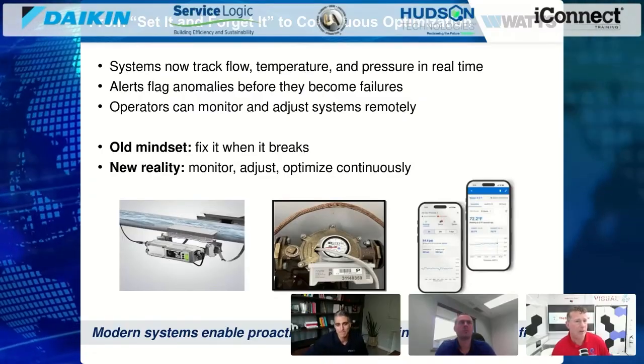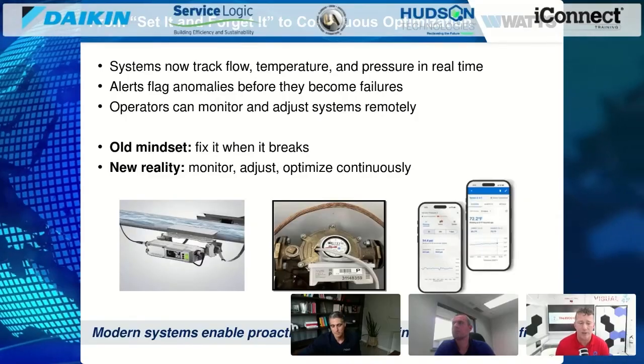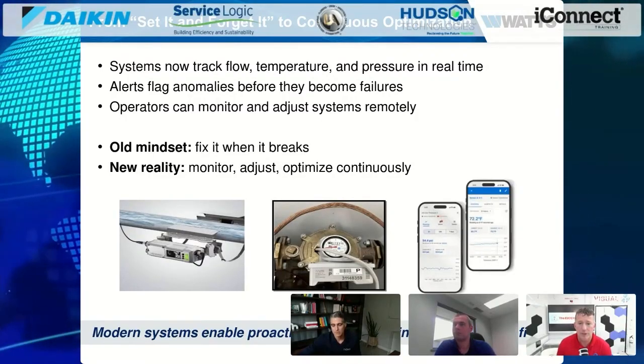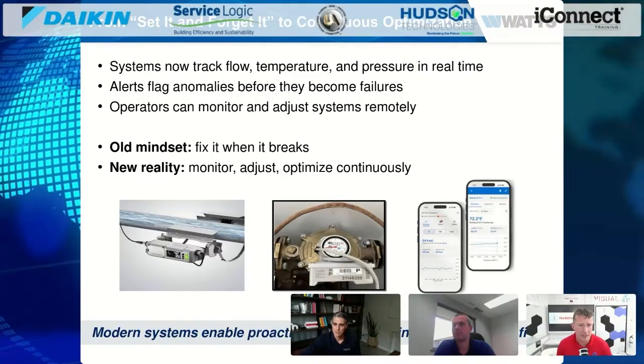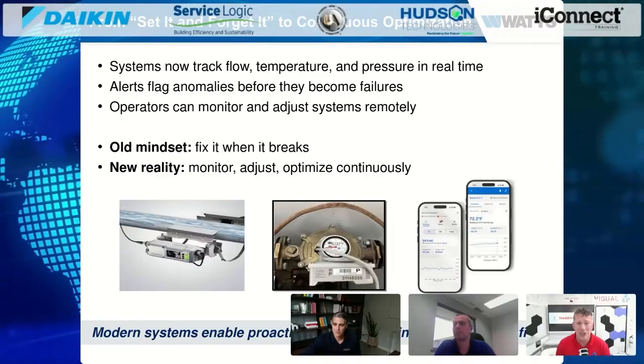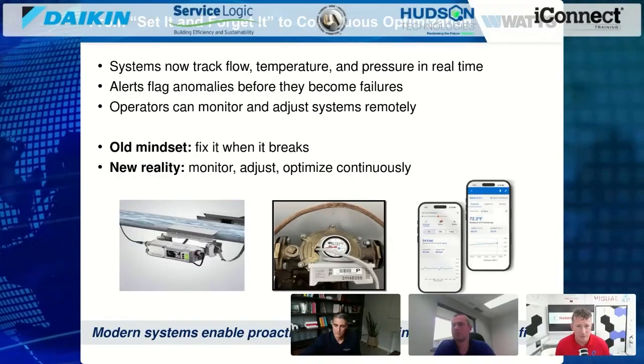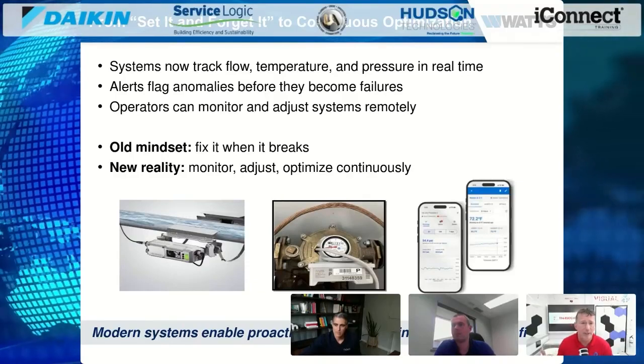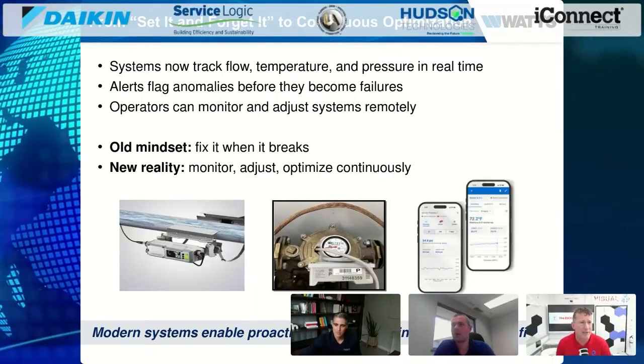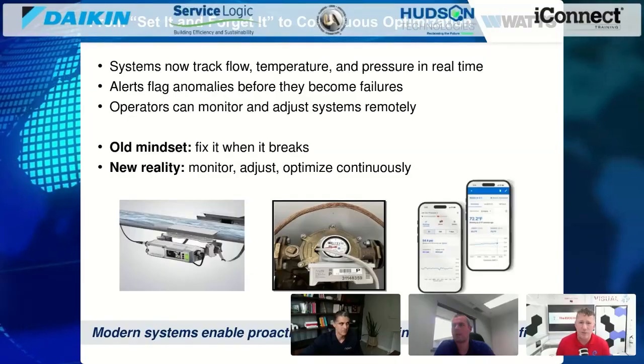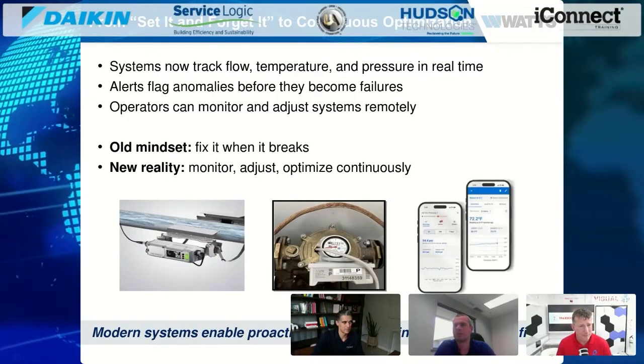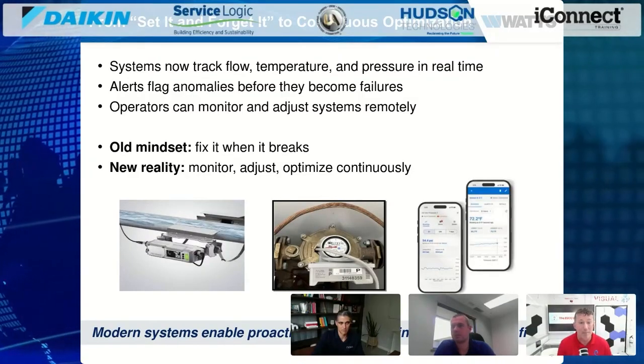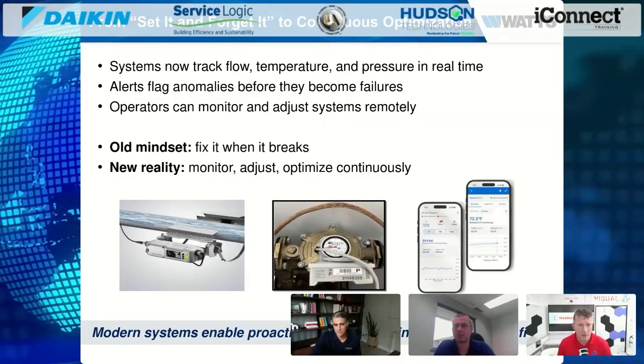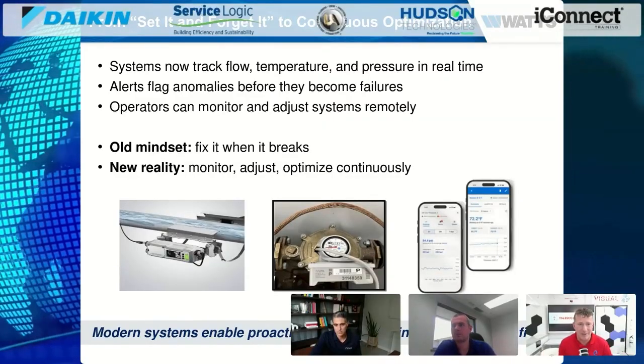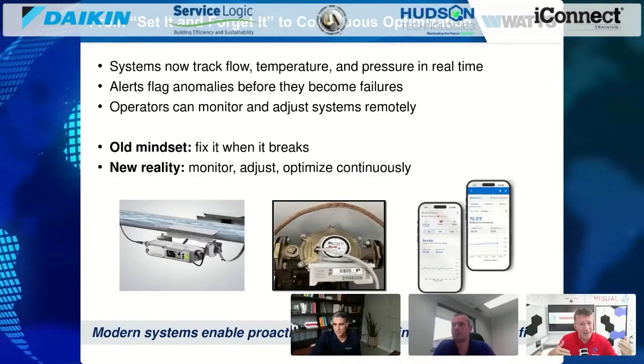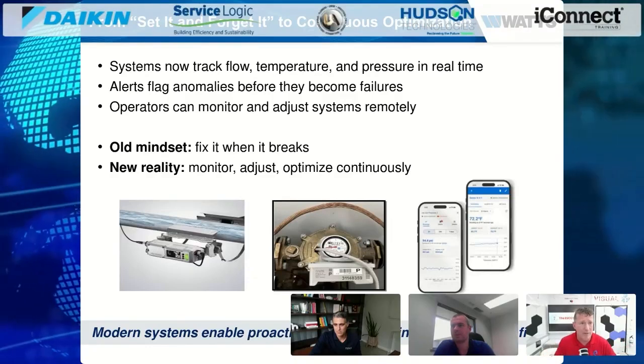It's amazing how much those three characteristics—flow, temperature, and pressure—affect heat pump systems. When we look at the runtime a heat pump takes for recovery, incoming water temperature is a huge factor in how long it takes for that heat pump to recoup the output temperature we're looking for. We're actually releasing a book soon at ESCO on high performance electric water heaters, focused on residential and some monoblocks, diving into how incoming water temperature affects the time it takes for a heat pump to produce the target water temperature. By monitoring and measuring all of this in real time, since most of these are variable capacity, our system can actually control capacity based on all of those parameters.